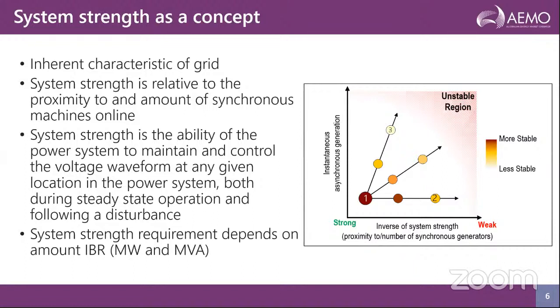Even if you have a large number of synchronous machines in the system, as you increase the penetration of IBR, the system strength reduces. And this is shown by number 3 in the figure. It's important to note that the system strength requirement depends on the amount of IBR. Sometimes it's megawatts, and sometimes it could be MVA, that is, the number of wind turbines or number of inverters you connect to the grid.